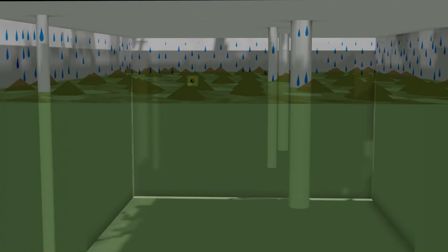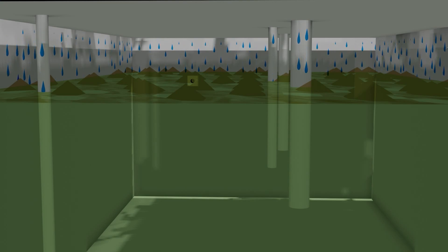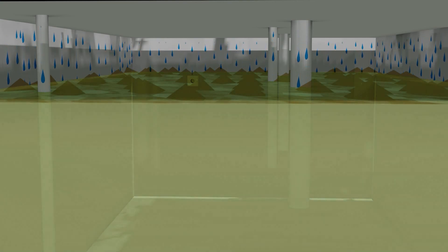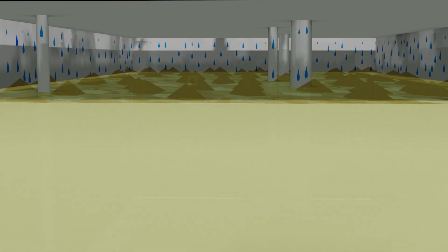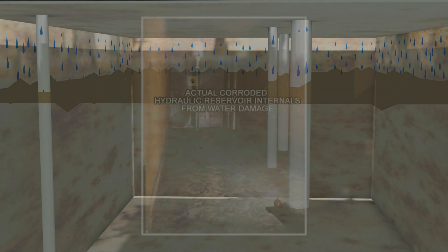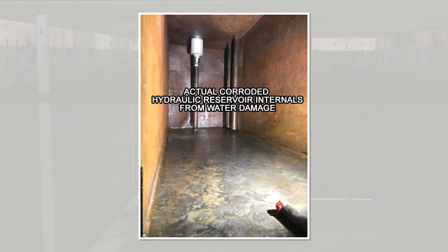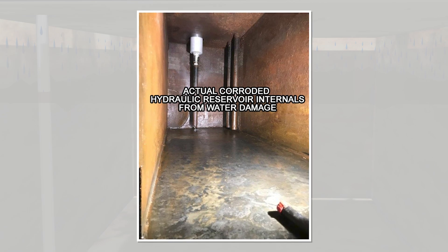Water contamination from any source in only a few hundred parts per million can turn oil milky or cloudy through oil-water emulsification. This, in turn, can cause gradual corrosion in the lubrication or hydraulic system, resulting in excessive particulate contamination of the oil.